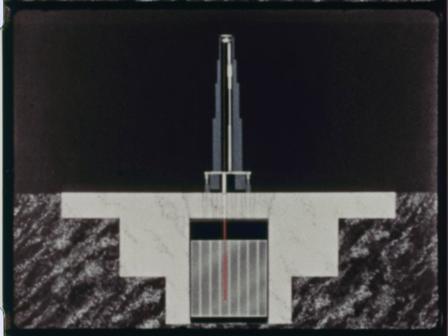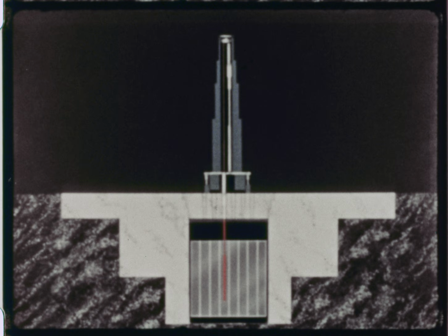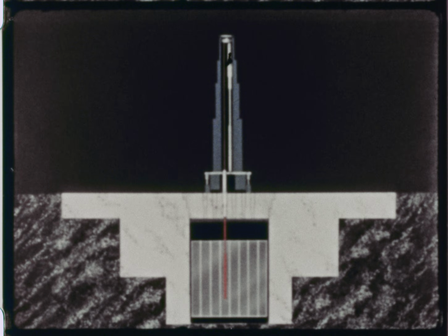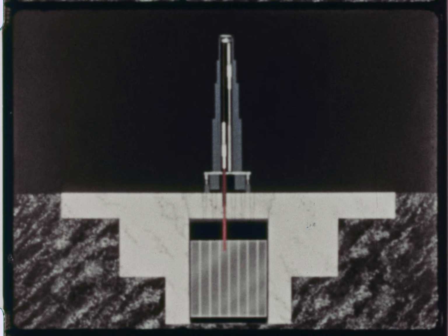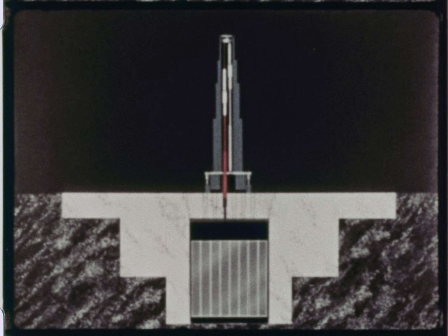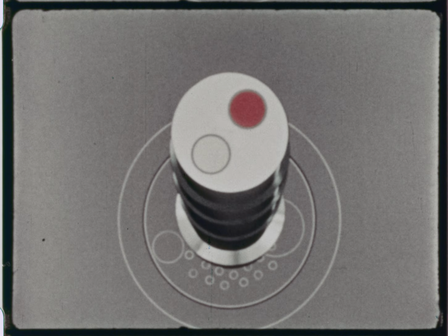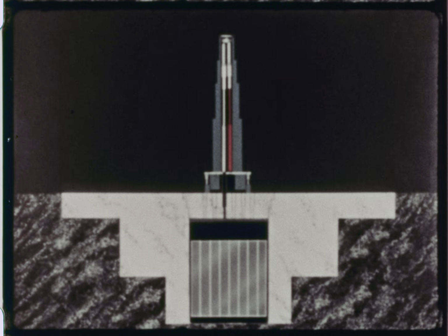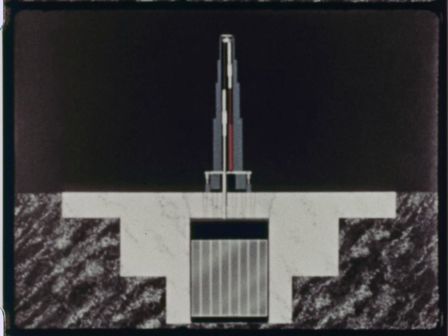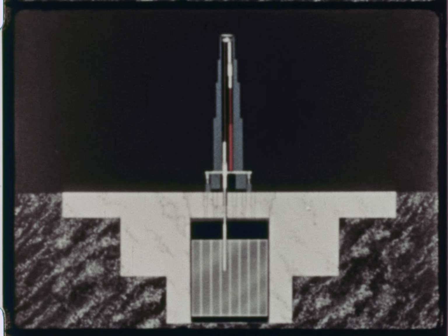A pickup device within the cask is lowered to engage the shielding plug of the used fuel element. The plug and spent fuel element are lifted out of the core as one unit. A revolving fuel support plate at the top of the cask is then rotated 180 degrees to position the new fuel element over the empty fuel channel in the core. The new fuel element and plug are lowered into place.